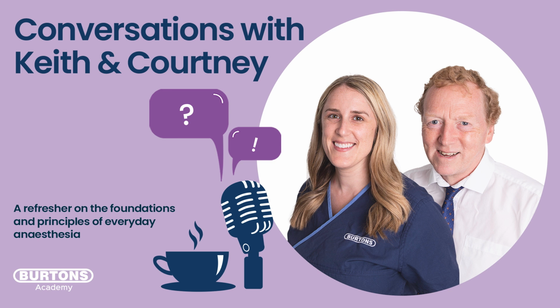Absolutely. I've looked at some studies on this, and detection of cyanosis has been looked into a lot, and it's very, very difficult to do. It's influenced by all sorts of things: skin color, and lighting, sunlight versus fluorescent lights versus tungsten lights, and the different colors of lights. In fact, I think the generally accepted view is that unless you get down to a saturation of 83% or less, it's very difficult to be accurate about diagnosis. And then we're in the danger zone.